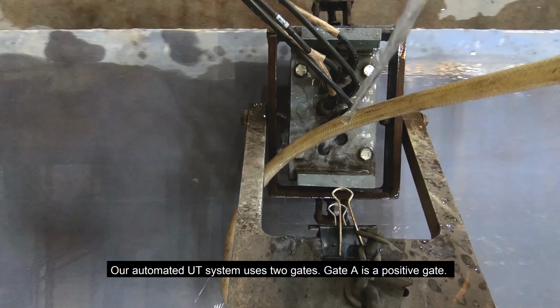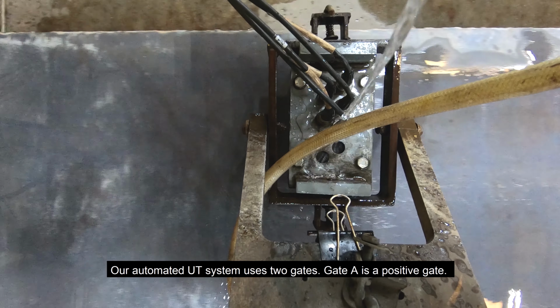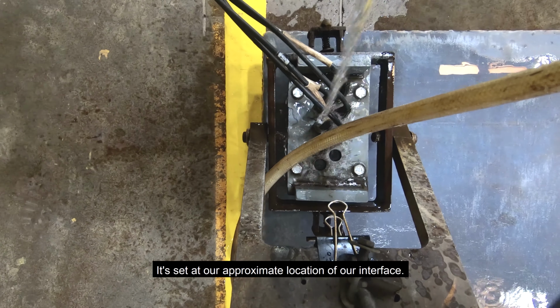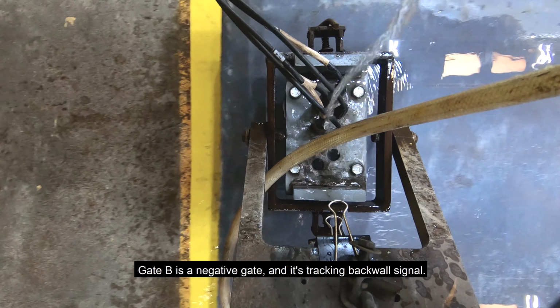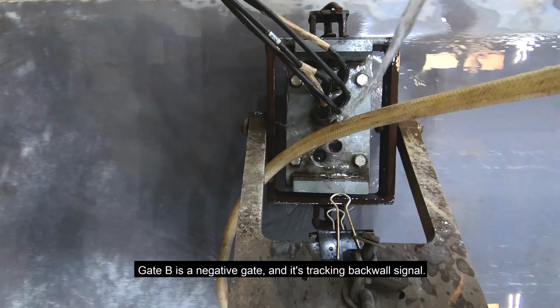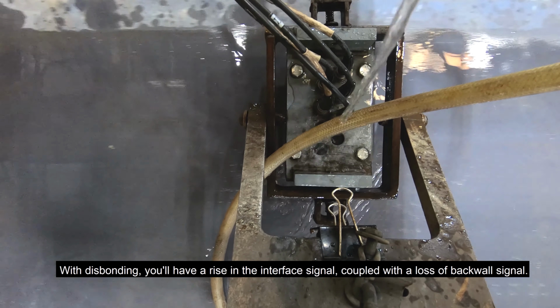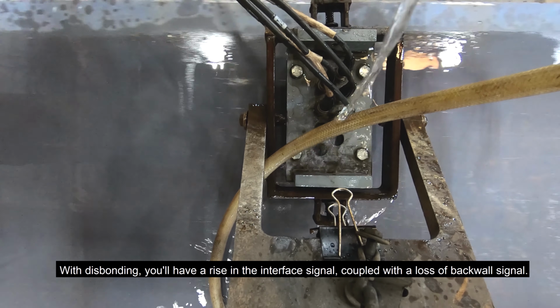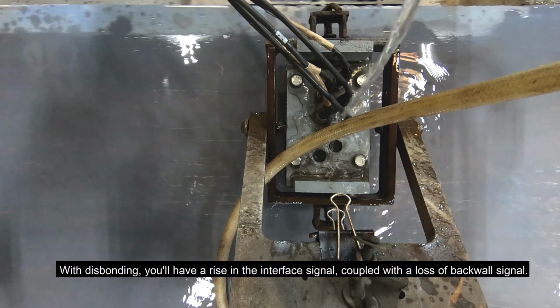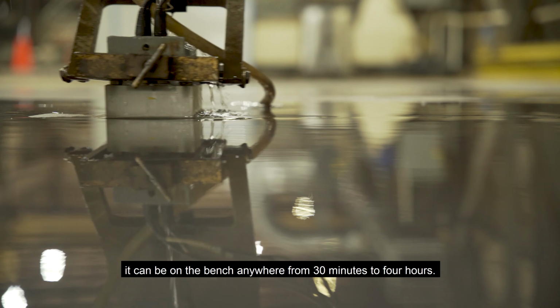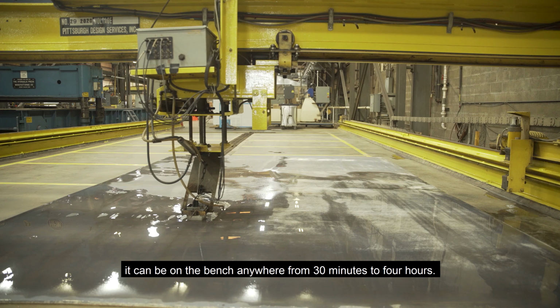So our automated UT system uses 2 gates. Gate A is a positive gate. It's set at our approximate location of our interface. Gate B is a negative gate, and it's tracking the backwall signal. With disbonding, you'll have a rise in the interface signal coupled with a loss of backwall signal. Depending on the customer specification and requirements, it can be on the bench anywhere from 30 minutes to 4 hours.